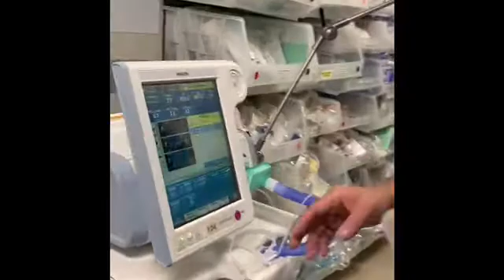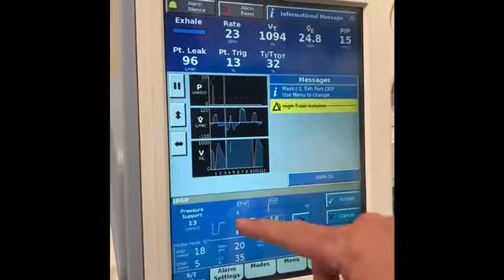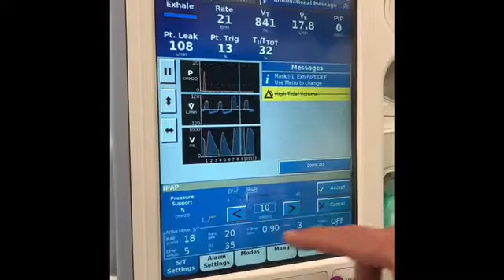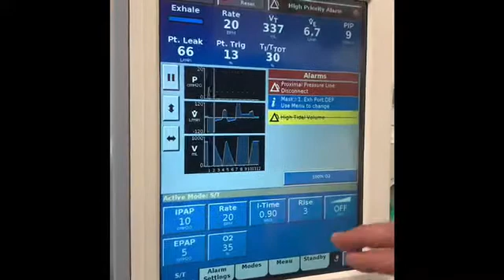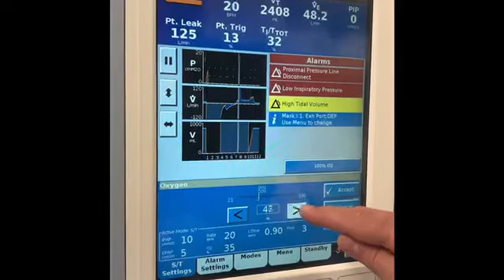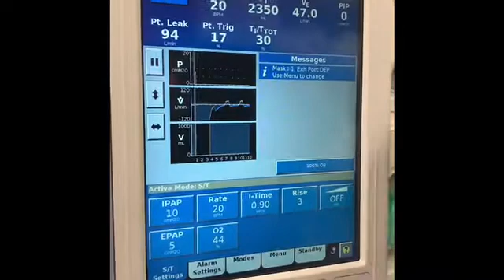A lot of air. So we have the BiPAP set. These are your different settings. So you have your IPAP here set at 18. Usually I'd say 10 and 5 is a normal setting for someone who's just on BiPAP at night. So you have your IPAP, your EPAP. We have our O2 set at 35. You can go up, you can go down. Just remember, you've got to hit accept.